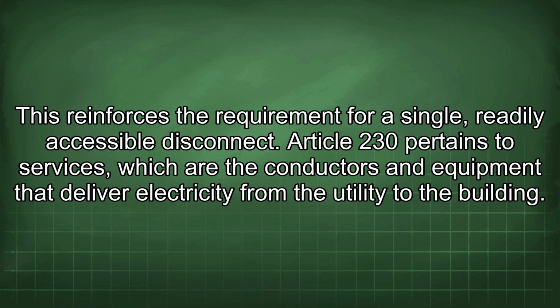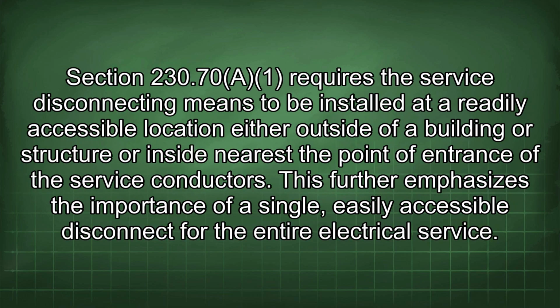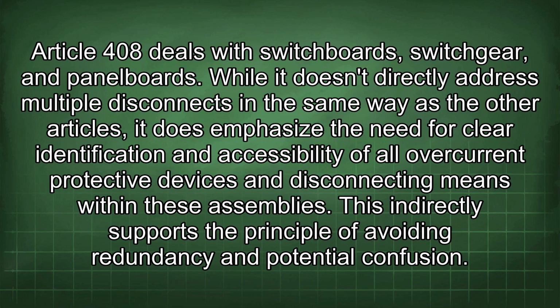Article 230 pertains to services, which are the conductors and the equipment that deliver electricity from the utility to the building. Section 230.70 requires the service disconnecting means to be installed at a readily accessible location either outside of a building or structure or inside nearest the point of entrance of the service conductors. This further emphasizes the importance of a single, easily accessible disconnect for the entire electrical service. Article 408 deals with switchboards, switchgear, and panel boards. While it doesn't directly address multiple disconnects in the same way as the other articles, it does emphasize the need for clear identification and accessibility of all overcurrent protective devices and disconnecting means within these assemblies. This indirectly supports the principle of avoiding redundancy and potential confusion.